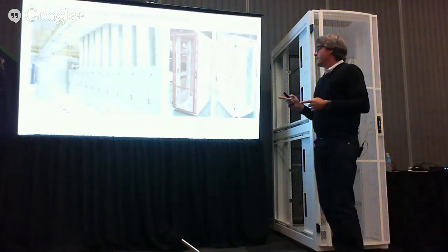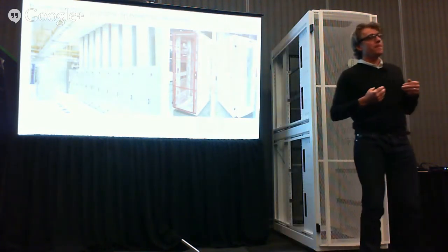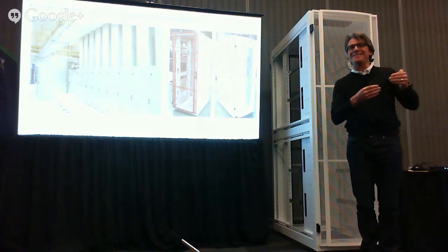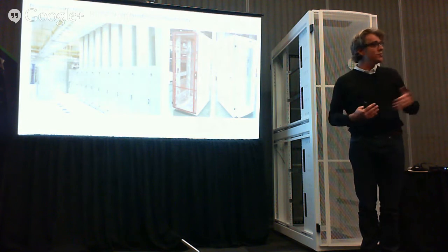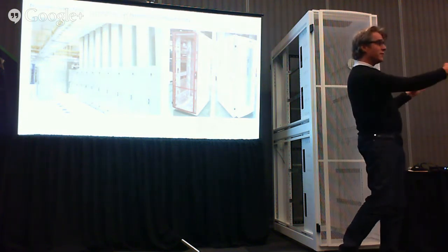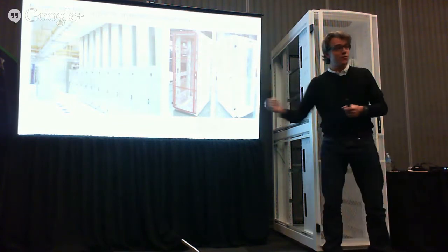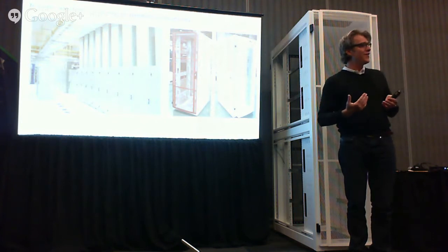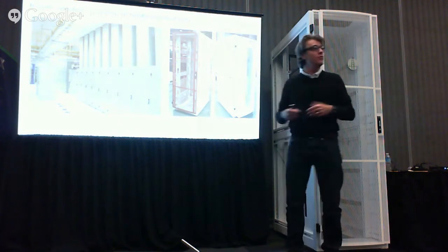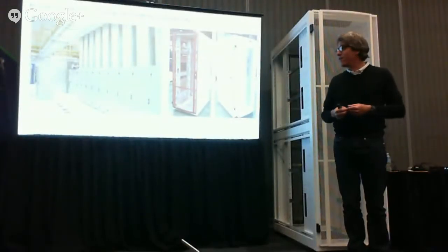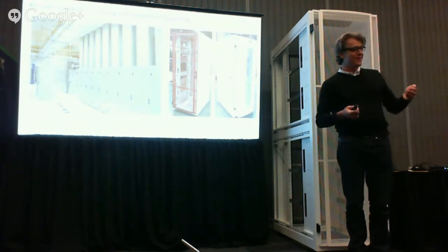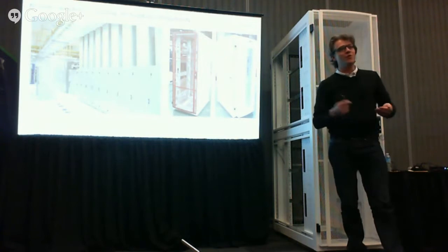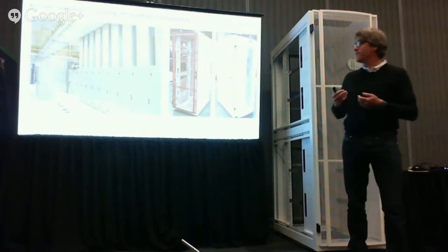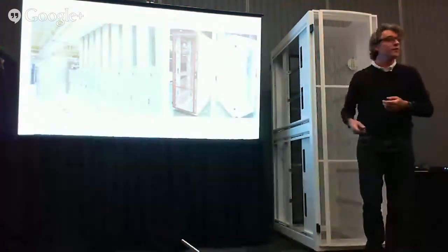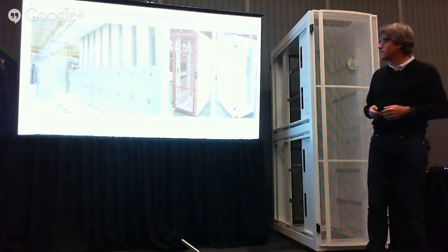Just on the chimney approach—it's clear that with more performing IT gear with very high delta T, servicing equipment from the rear is becoming a big issue. That's one key reason Open Compute designed a rack serviced only from the front. With these racks, when I open the rear door I'm pumping air at 130 to 135 degrees Fahrenheit, and the chimney system pulls air through, creating some type of bypass, making the IT technician's work feasible without a limited schedule to access the aisle. That's why a lot of our customers go with chimney style containment to cope with very high exhaust air temperature.